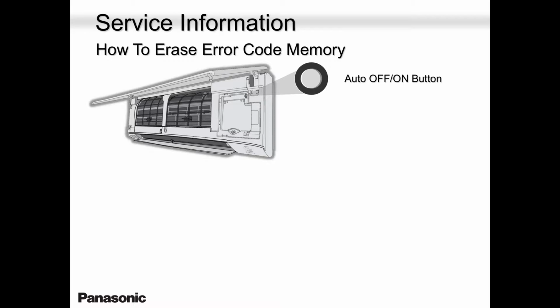Some guy would be called for servicing the unit, for just cleaning the unit, and then tries to be a little bit inventive, or curious. They go into the error code and they find an error code and they try and fix it. Only fix an error code that the timer light was blinking. Do not fix any error codes stored inside, because it could be an error code that does not belong to you.